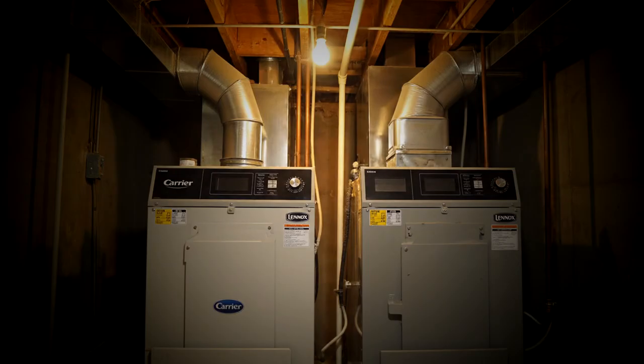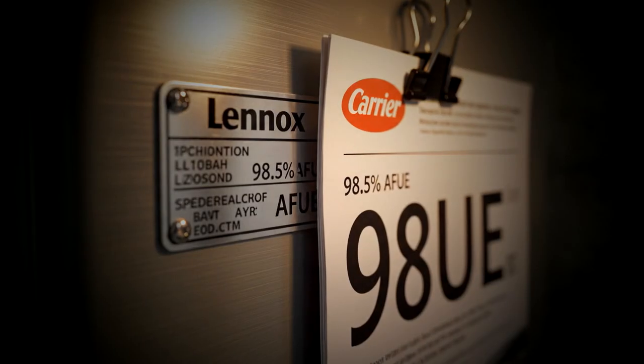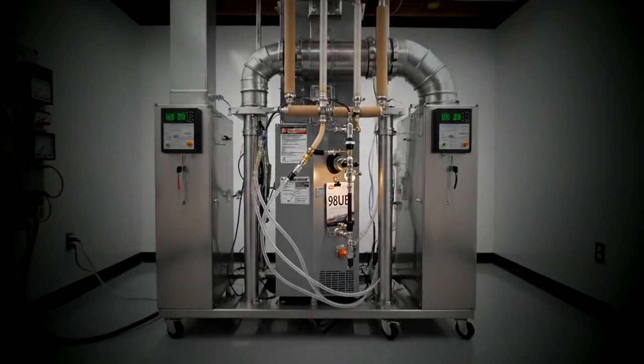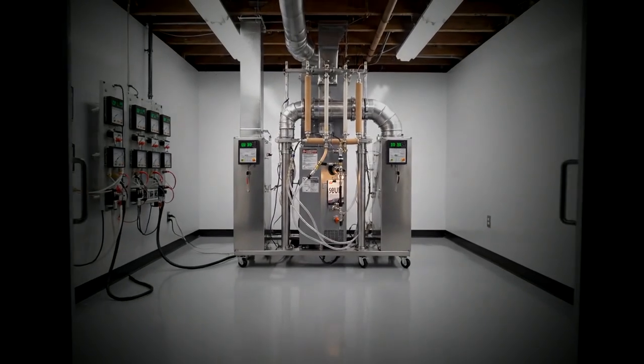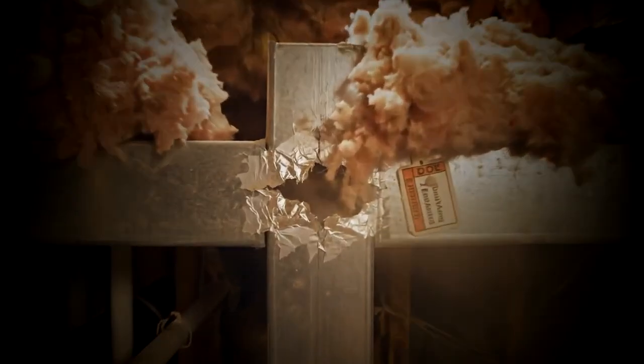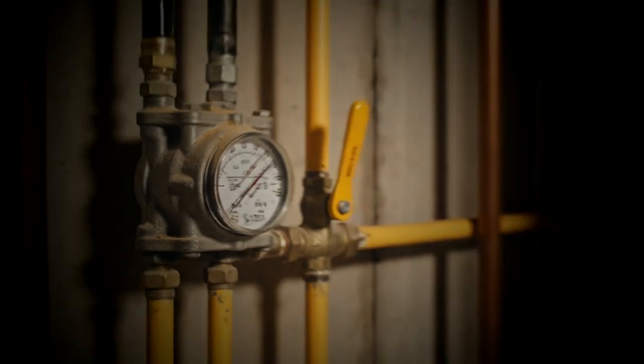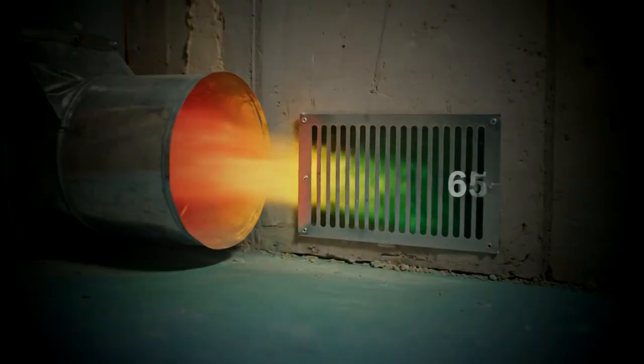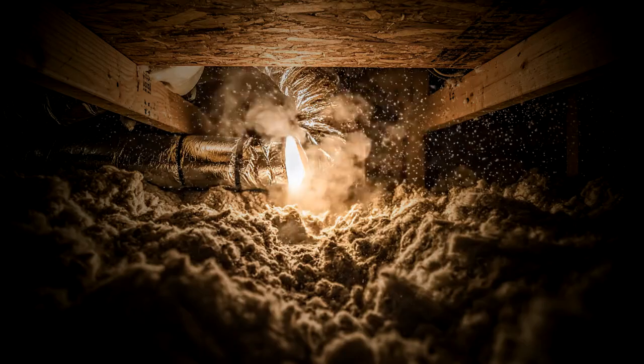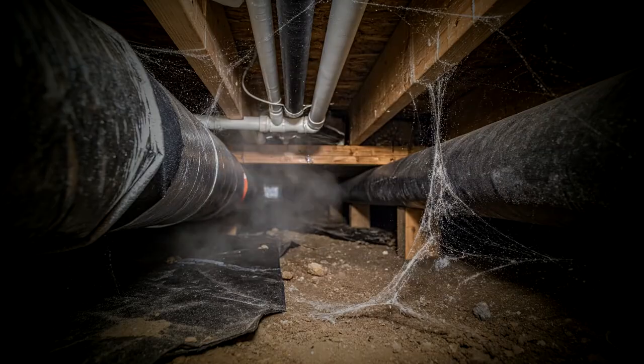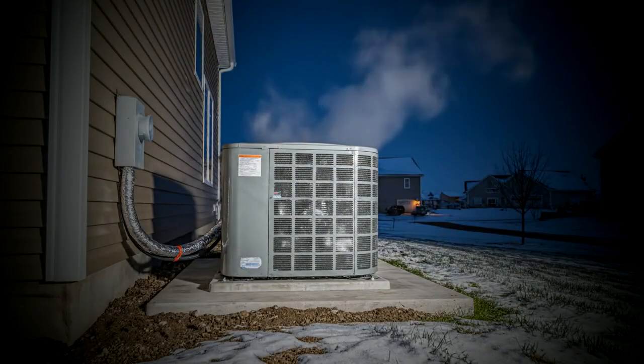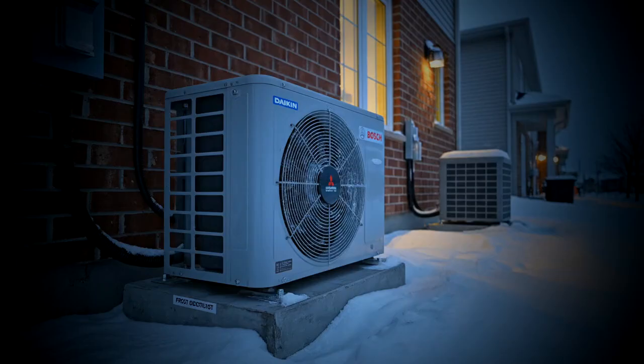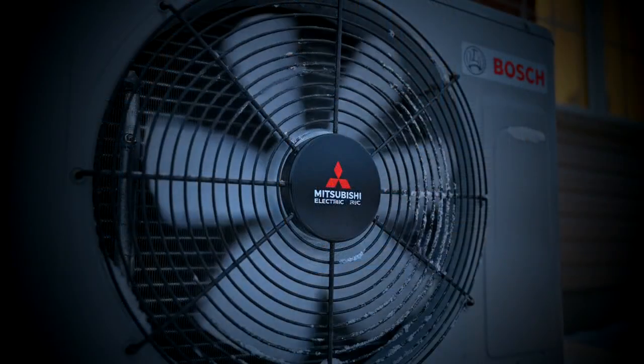Now, here's the mechanism that makes the math work. A standard natural gas furnace operates at between 80 and 95% annual fuel utilization efficiency, AFUE, under optimal conditions. The highest efficiency gas furnaces on the market today, from manufacturers like Carrier and Lennox, advertise 98.5% AFUE. That number is real under laboratory conditions. Under real-world installation conditions, duct leakage averaging 30% in most existing homes, according to the U.S. Department of Energy, effective efficiency drops to between 65 and 75%. You are paying for 100% of the gas. You're getting 65 to 75% of the heat. The other 25 to 35% is heating your attic, your crawl space, and the outside air.